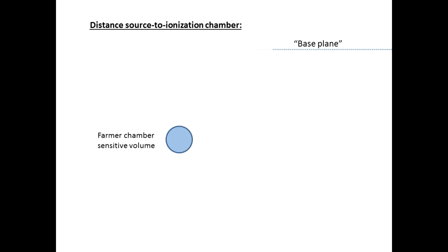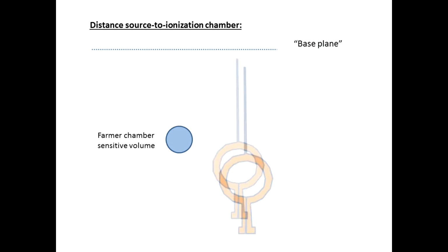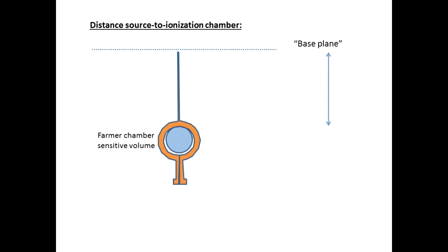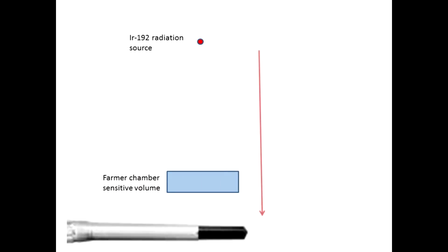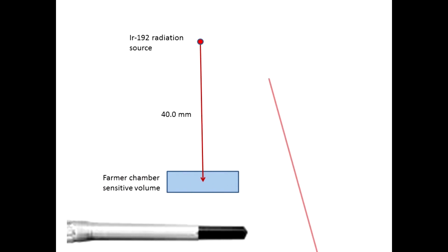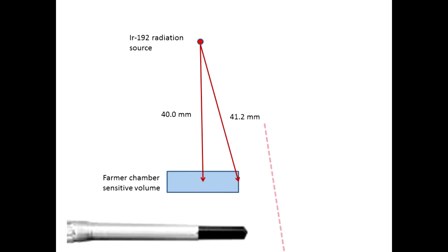And what is the source to chamber distance? To calculate it, we should sum up the empty device constant, the distance from the base plane to the upper surface of the ionization chamber. Then the next summand is the radius of the ionization chamber. Next step, we should take into account displacement of the ionization chamber center due to the quite large longitudinal dimension of the chamber. If the center of the chamber is placed at 4 cm distance, the tip of the chamber will be at 41.2 mm distance from the source.